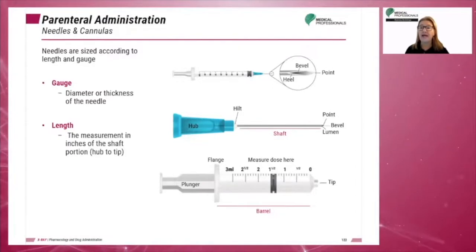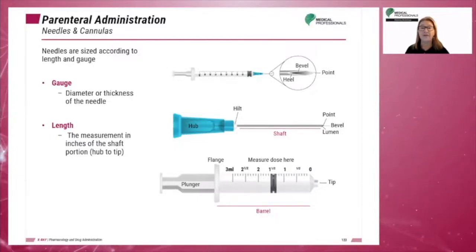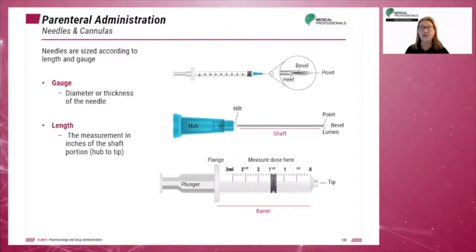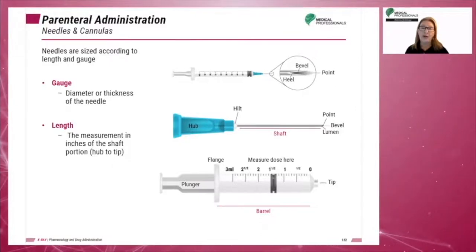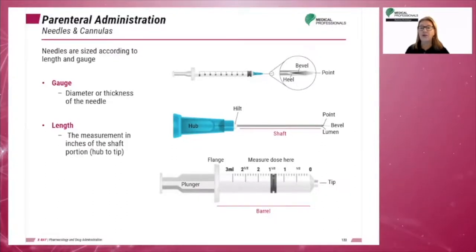Needles are sized according to length and gauge. Gauge is the diameter or thickness of the needle. The length is the measurement in inches or centimeters of the shaft portion from the hub to the tip. The smaller the diameter of the opening or lumen, the larger the gauge number.